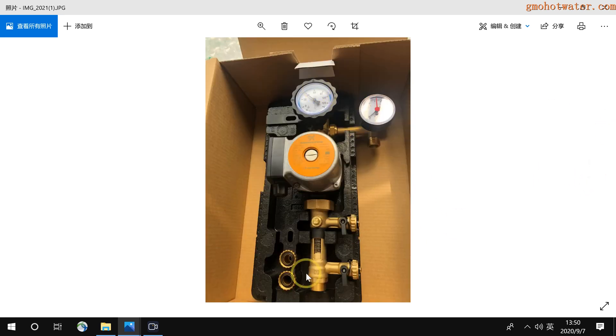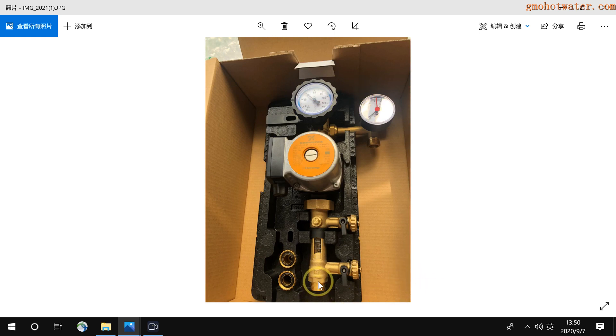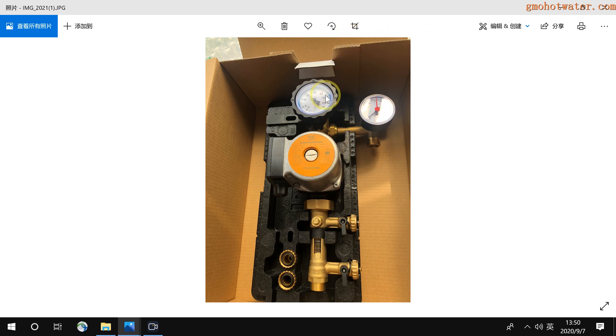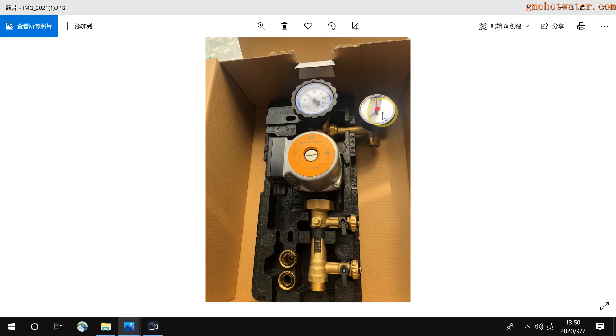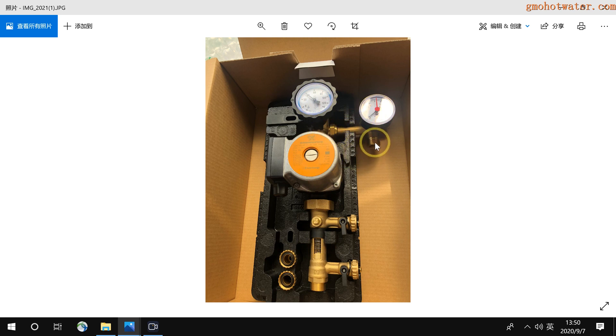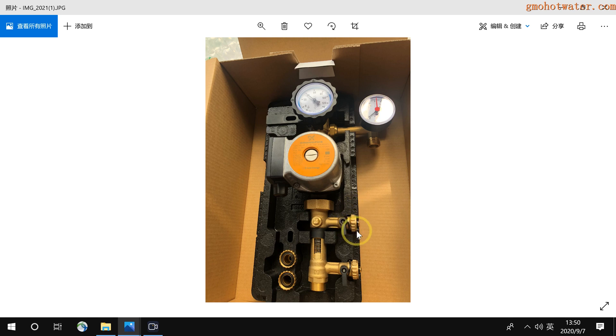Inside is this picture. The cold water from the tank goes inside from the bottom and up, and then to the collector. This is to show the temperature inside the pipe, and here is the pressure gauge to show the pressure in the pipe. Here is the connection for the expansion tank. Because we are using water circulation, we can block it. We can borrow one brass plug from here to block this connection.